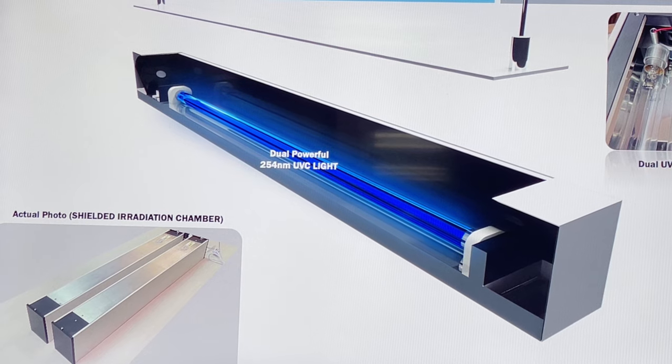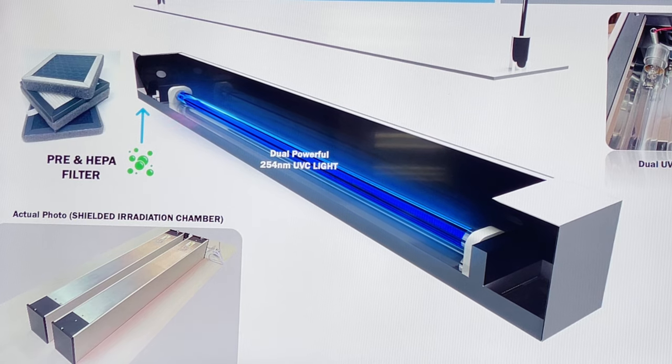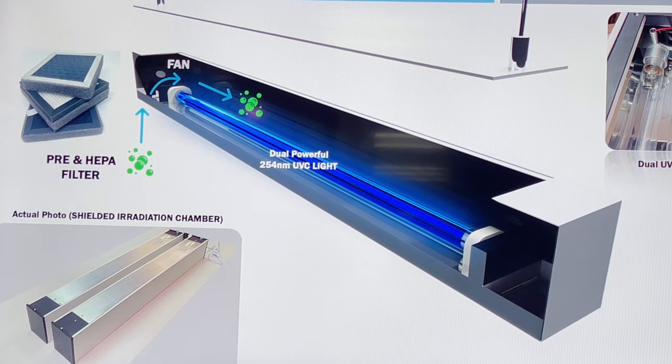So this is how it works. I just wanted to clearly explain how it works, okay? So those are the virus particles. And you can see the virus particles going into the fan because the fan, using differential pressure, sucks the air. Okay? And then it passes through a series of filters. Like I said, we have a pre-HEPA filter inside. Then it will be sucked into the chamber. The chamber is enclosed. You can see there is this dual lamp at the back.